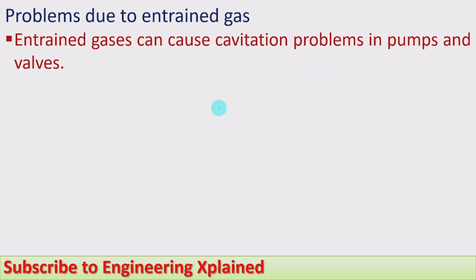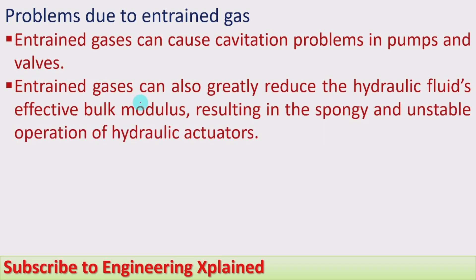Entrained gases can cause the cavitation problem in pumps and valves. Cavitation means that at a lower pressure region, when flowing through the pipeline, vapor is formed due to low pressure reaching the vapor pressure. When the fluid moves to pumps and valves where pressure increases, those bubbles collapse, and during collapsing, pitting of the surface takes place — the surface gets damaged. Entrained gases can also greatly reduce the hydraulic fluid's effective bulk modulus, resulting in spongy and unstable operation of the hydraulic actuator.